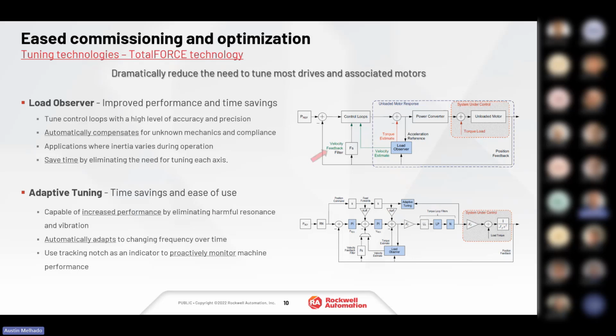Adaptive tuning learns those mechanical dynamics and automatically tunes them out. From the customer perspective, this gives them, in many cases, a tuneless out-of-the-box experience. They don't need to become a tuning expert or retain a special skill set on their staff. Not that there's anything wrong with being a tuning expert, but tuning a drive could take up to 4 hours at times, especially on complex variable load applications.